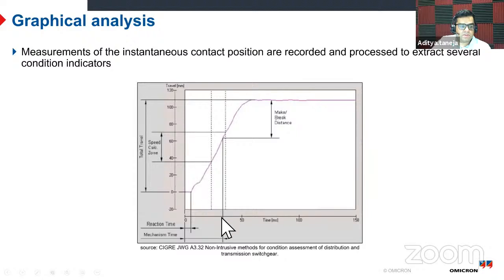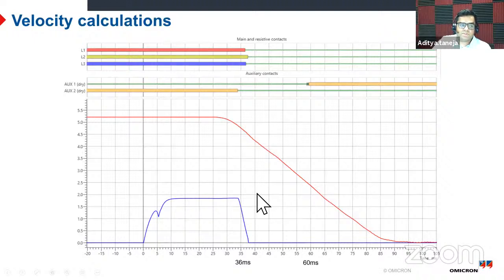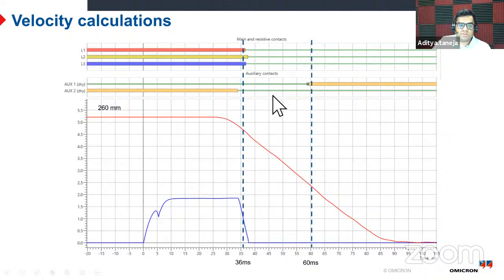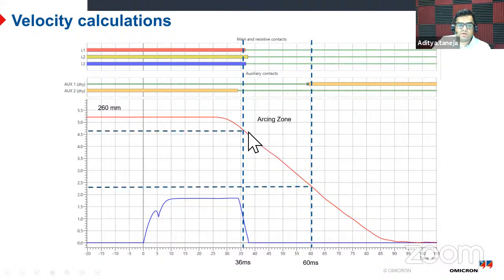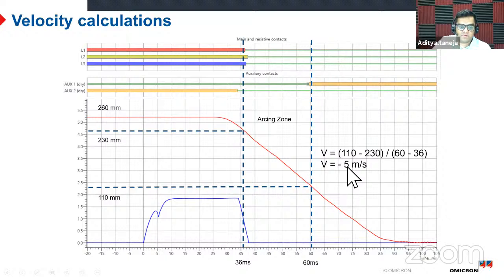So what the CIGRE brochure says for non-invasive methods is that you have to measure the make-break distance, the speed and the total travel, and also the reaction time, the time taken for the breaker to start reacting to the command, and the time the mechanism takes to open. All these parameters are important and should be recorded. Looking back here, the total distance was 260 millimeter. Then we saw the arcing zone, and with that we take the corresponding points on the curve, that is 230 and 110, and then we calculate the average speed, which is 5 meters per second.